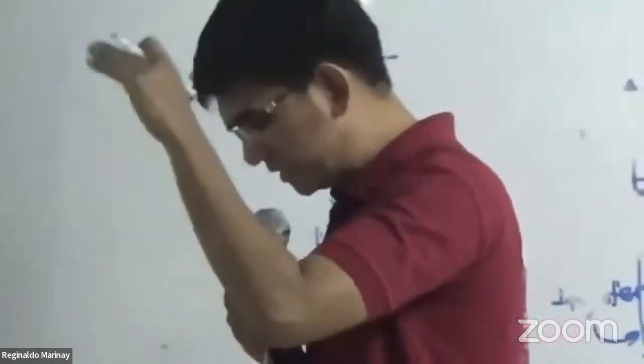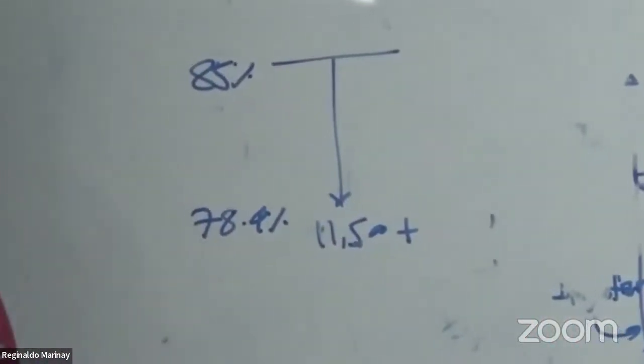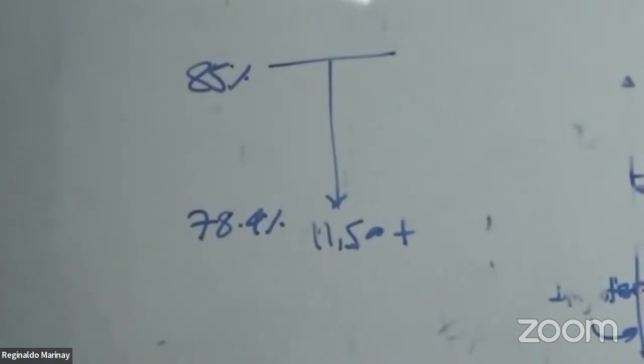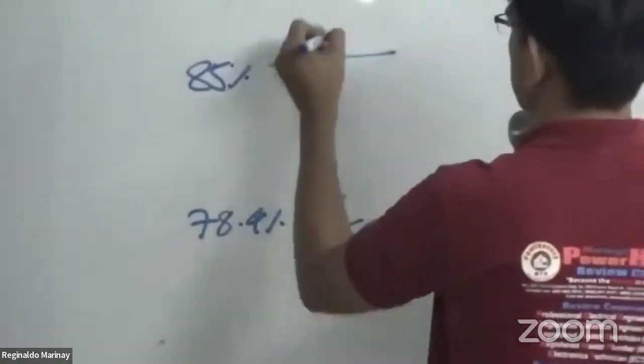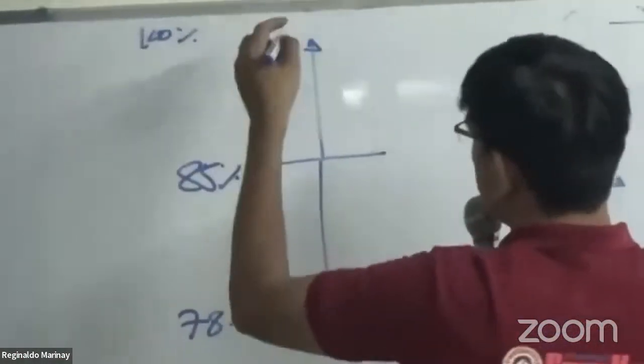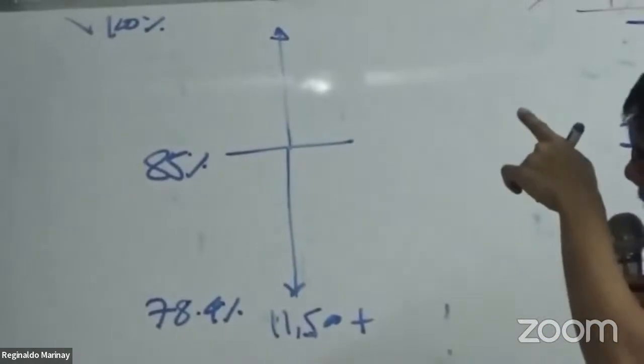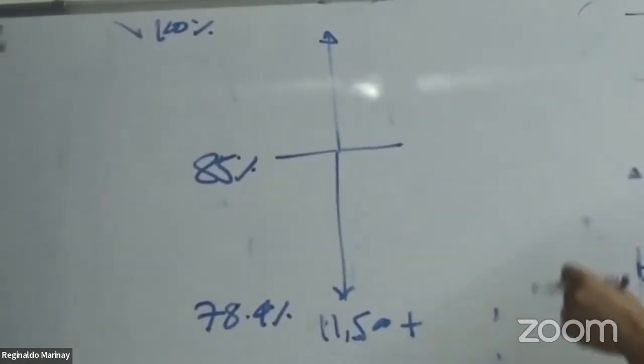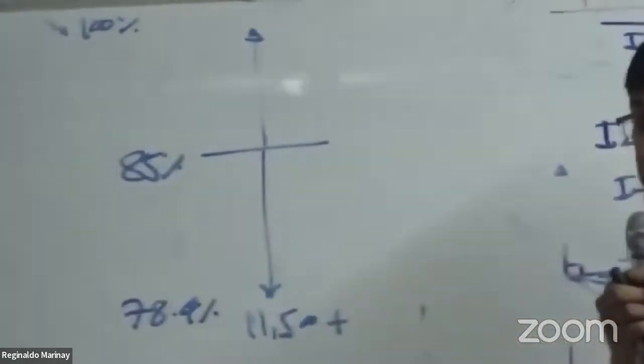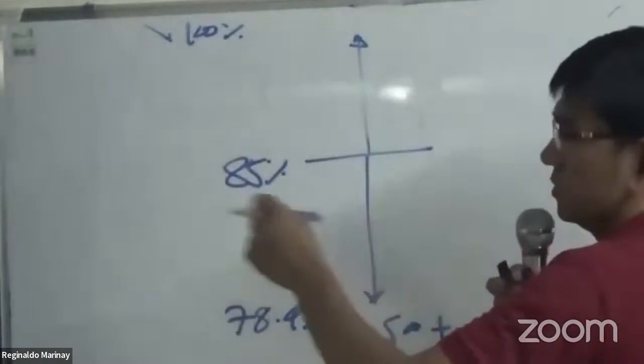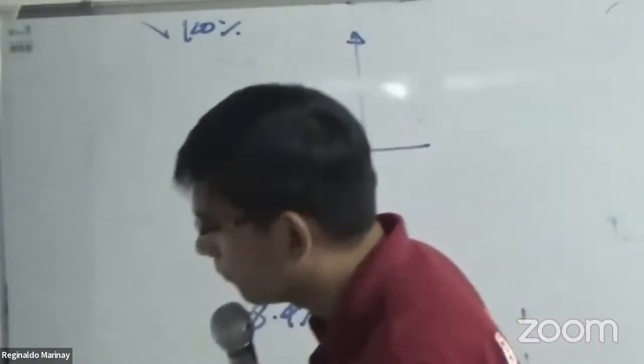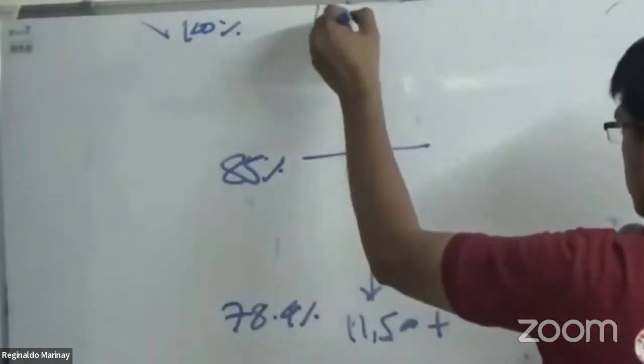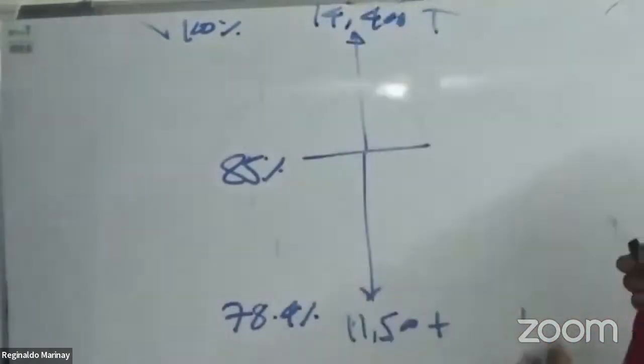Now, to maximize and see the maximum discount, this is an exaggerated power factor of 100% - there is a discount of 14,400 plus. Although I told you not to correct your power factor to 100%, maybe 98, 99 is fine. But let's go back to basics - 92 to 96% would be good. I saw this in the Electrical Engineering magazine of IIE. So we have 14,400 plus.